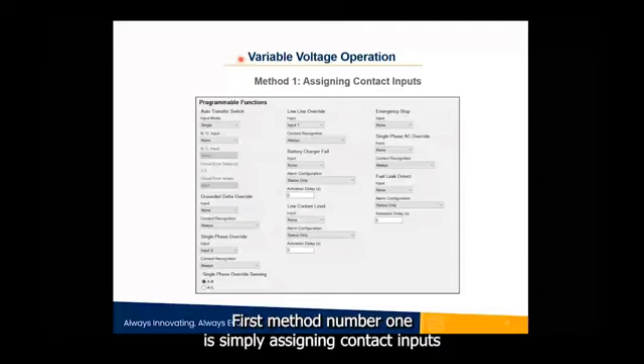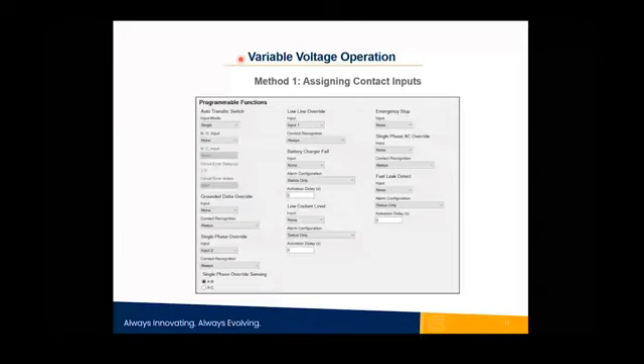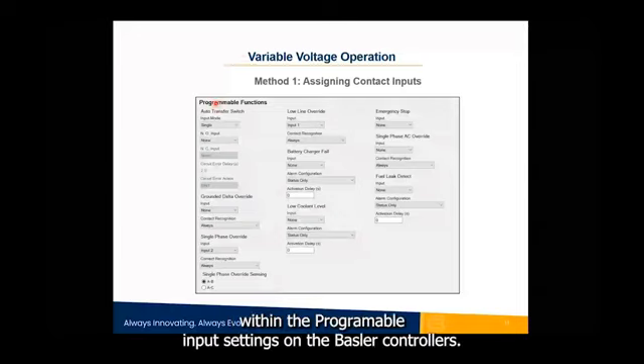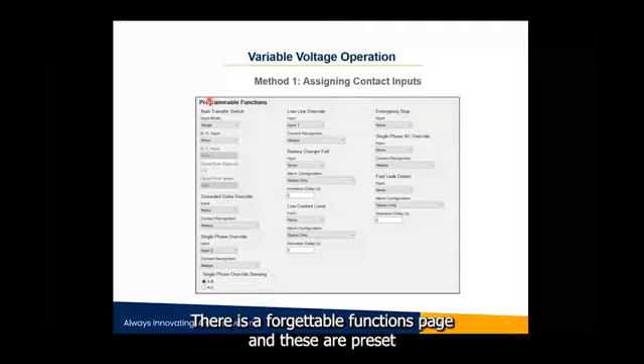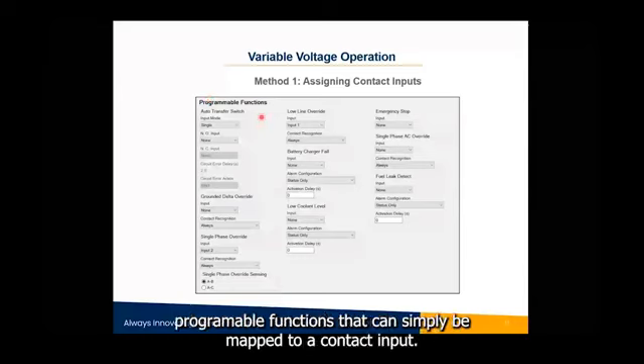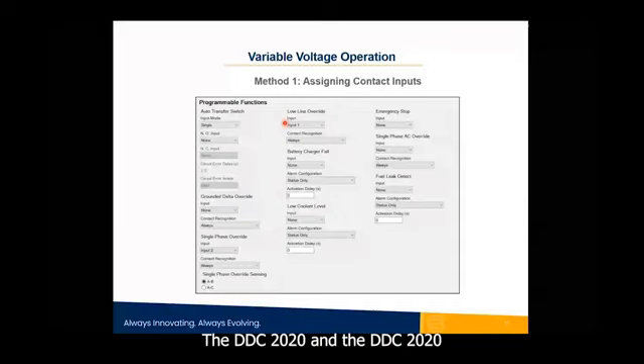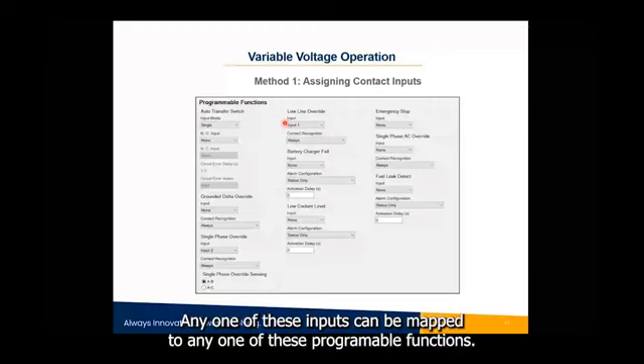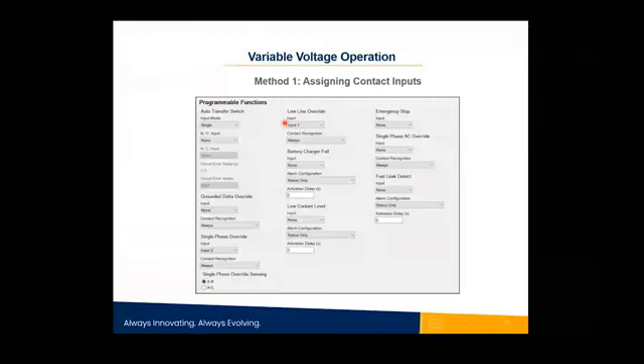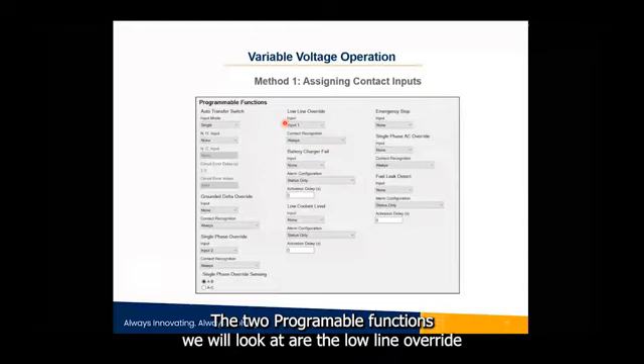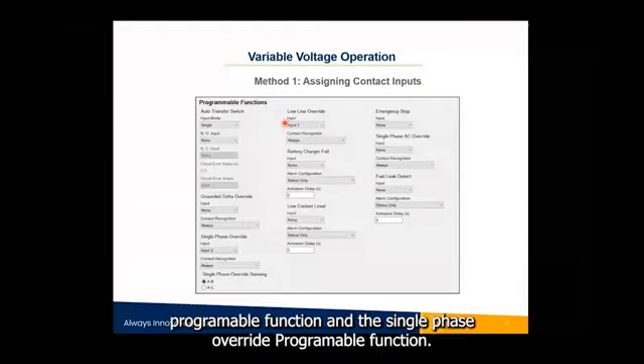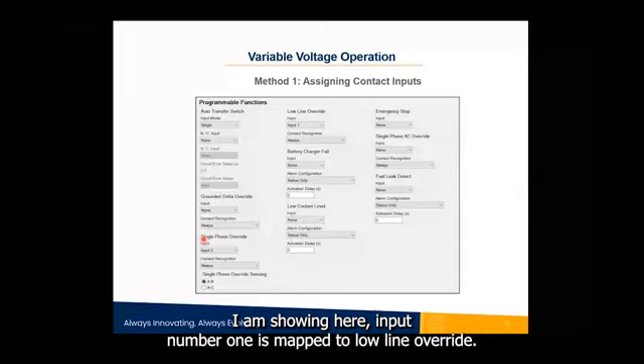First, method number one is simply assigning contact inputs. Within the programmable input settings on the Basler controllers, there is a programmable functions page, and these are preset programmable functions that can simply be mapped to a contact input. The DGC 2020 and the DGC 2020 HD each have 16 contact inputs. Any one of these inputs can be mapped to any one of these programmable functions. The two programmable functions we will look at are the low line override programmable function and the single phase override programmable function. So in this example I am showing here, input number one is mapped to low line override.